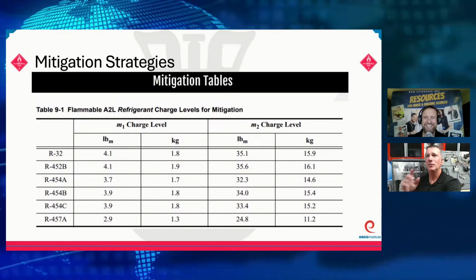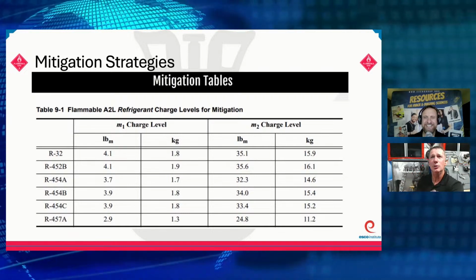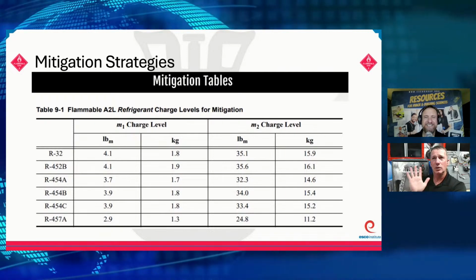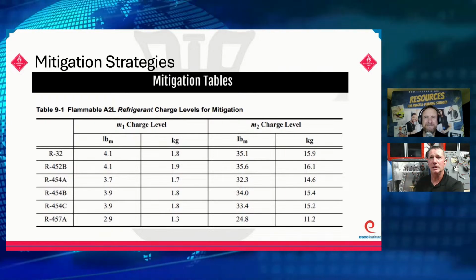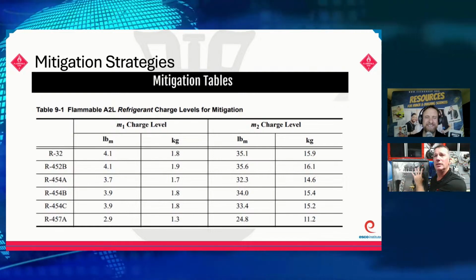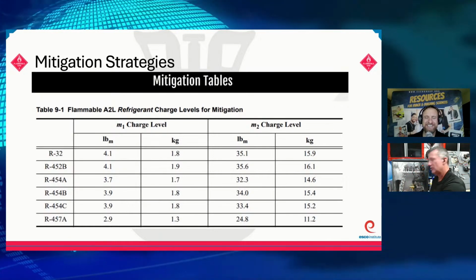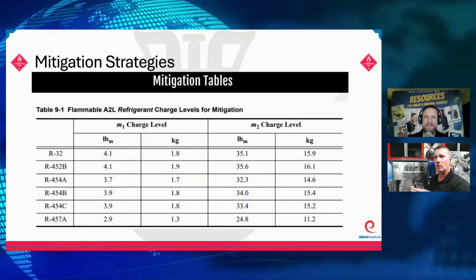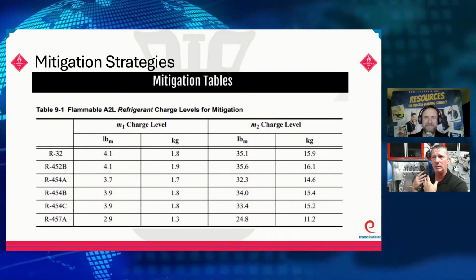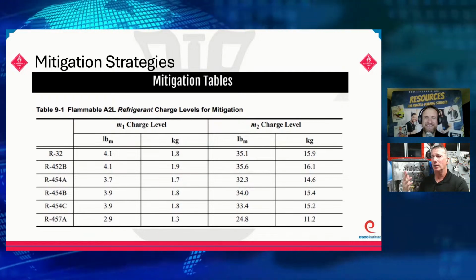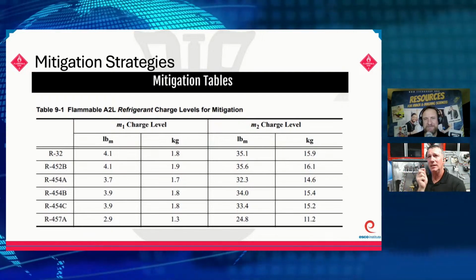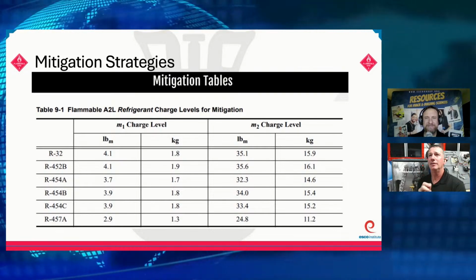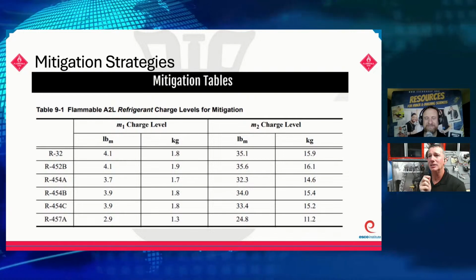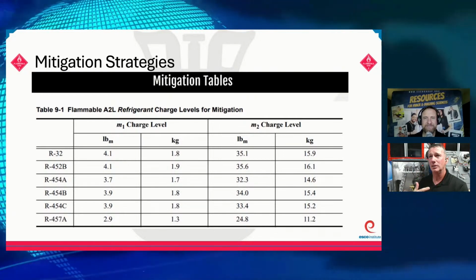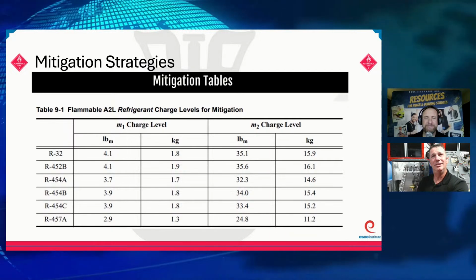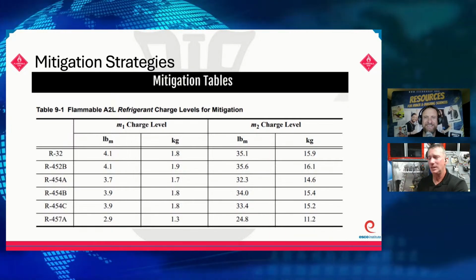Okay. So on this particular unit, let's take this new installation, and assume for a moment that this is a complete new system installation. This is my R32 indoor cased coil with its refrigerant detection sensor. We have our R32 condensing unit or heat pump outside. We have a new gas furnace, but it hasn't been updated to the newest version of control board that has the mitigation sequence built into it. What would I need to do to have a sequence of mitigation with that, Ty?